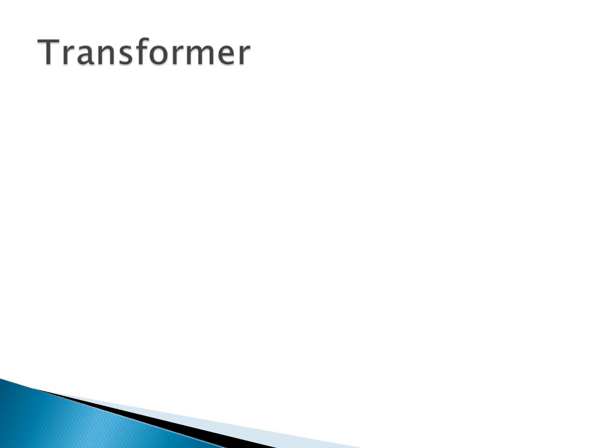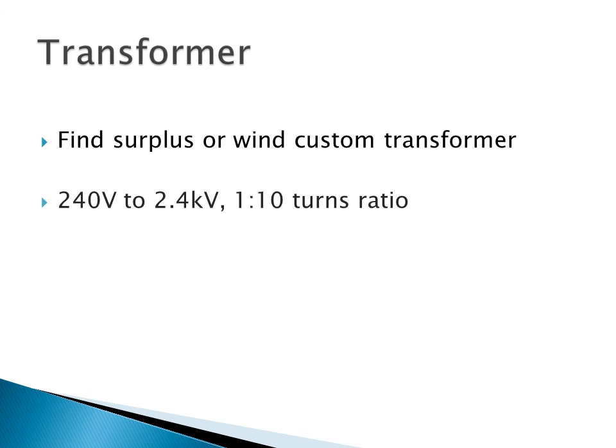The solution to this, of course, is to use a step-up and step-down transformer. These can be found surplus in a lot of different places, or they can be custom-made for particular applications. If we were to, say, consider using a 240 to 2.4 kV transformer, this can be custom-wound or found. We can reduce the losses by a factor of 1 over 100, in terms of losses in the copper.